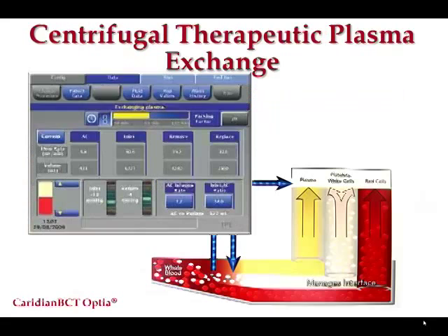Looking at the chamber: the edge of the centrifuge generates centrifugal forces outward. The most dense components — red blood cells — settle on the outside. Then a layer of less dense material: platelets and leukocytes sitting on top of the red cells, just like in your hematocrit tube. The least dense material is the plasma. Once the blood is separated into these components, we can selectively take off the abnormal piece and exchange it for a non-pathological component. This is called centrifugal apheresis.